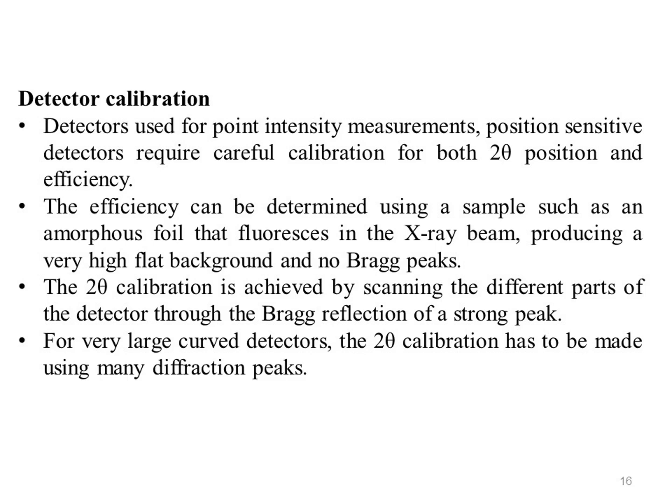The calibration can be checked by measuring the complete pattern of a reference material. Sealed gas filled PSDs should be recalibrated whenever the gas is replenished, in contrast to detectors with a continuous flow of gas that need checking regularly.